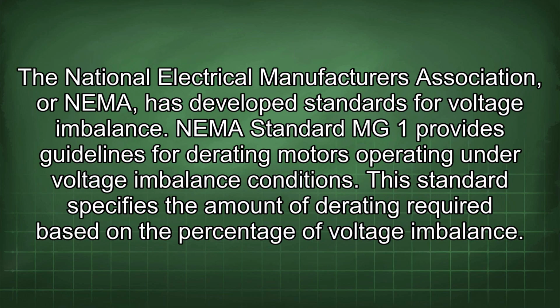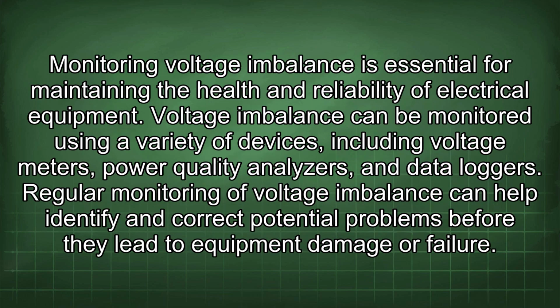The National Electrical Manufacturers Association, or NEMA, has developed standards for voltage imbalance. NEMA Standard MG1 provides guidelines for derating motors operating under voltage imbalance conditions. This standard specifies the amount of derating required based on the percentage of voltage imbalance. Monitoring voltage imbalance is essential for maintaining the health and reliability of electrical equipment. Voltage imbalance can be monitored using a variety of devices, including voltage meters, power quality analyzers, and data loggers. Regular monitoring of voltage imbalance can help identify and correct potential problems before they lead to equipment damage or failure.